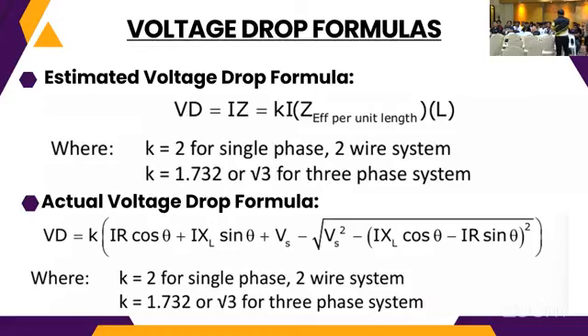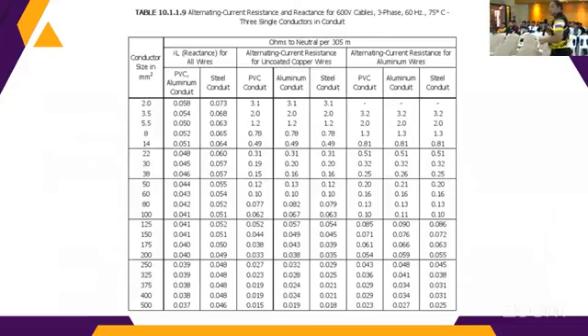Our voltage drop depends on the power factor. If this is lagging, then we need to get the voltage drop of the resistance. Then the voltage drop of the reactance is perpendicular to the resistance drop. Correct? Then from the origin, you need to draw a line to the tip of the reactance drop, so that we have a triangle. So we come up with this formula: voltage drop is equal to K times I times R cosine theta plus XL sine theta, plus the square root term. Again, K is 2 for single phase and square root of 3 for a three-phase system. Okay, next.